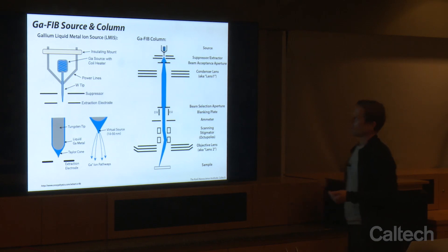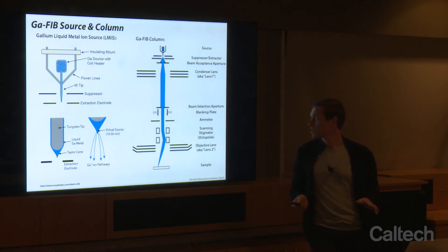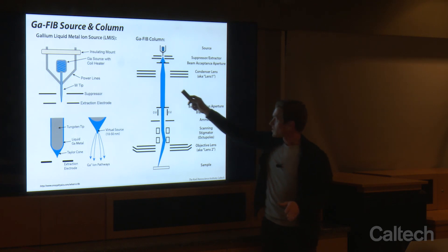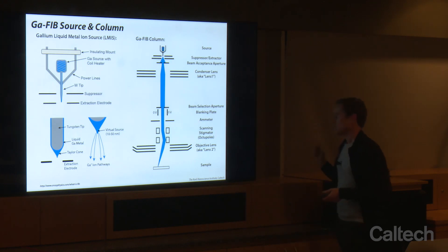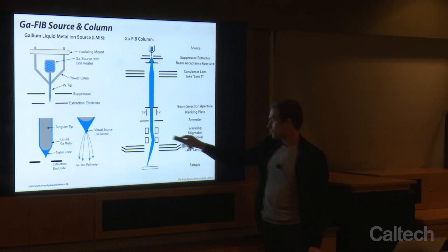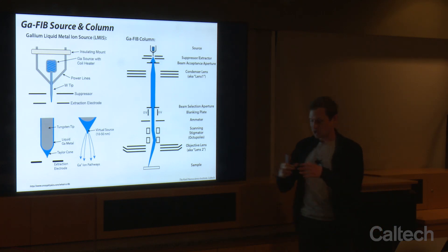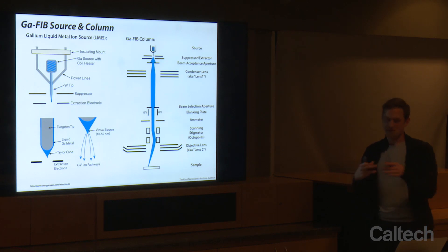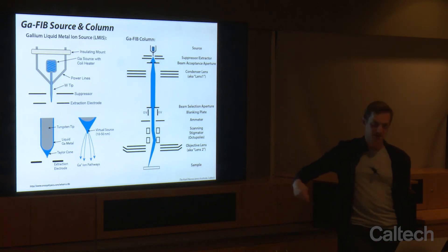Here's our column. We have the source at the top with the suppressor and extractor. A beam acceptance aperture blocks most of that two microamps of current. The beam enters the condenser lens, and we can change how the beam is spread over the aperture. When we change current, we're mostly changing the beam selection aperture — just the size of the hole the beam passes through. The beam then comes down through the scanning and stigmator octupoles, which are responsible for both scanning the beam over the surface and changing the profile of the beam. If we have astigmatism, we get an elliptically shaped beam; we want a round beam for a nice small probe size. Then it passes through the objective lens where it gets focused down to a final point and scanned across the sample.